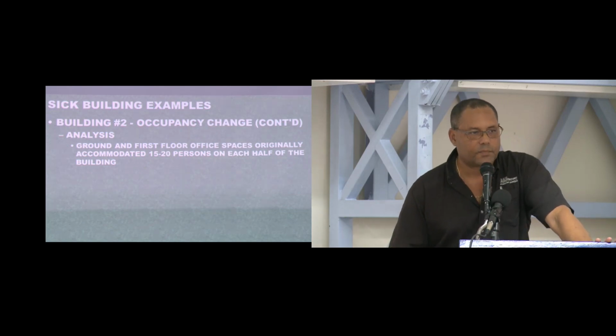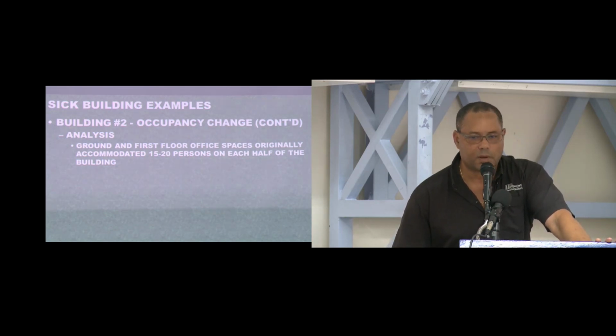So what happened here was that the company's business model changed. You used to have 15 to 20 people on each side of the floor, an air handling unit serving each side of the floor. People started traveling for work or working from home, so you ended up with 5 or 6 people. The office is empty. All of a sudden, your unit that is designed to deal with the load from 15 to 20 people is dealing with a load of 5 to 10 people per floor. And you have no control over your outdoor air intake, your building is negative. So now your system is too big.